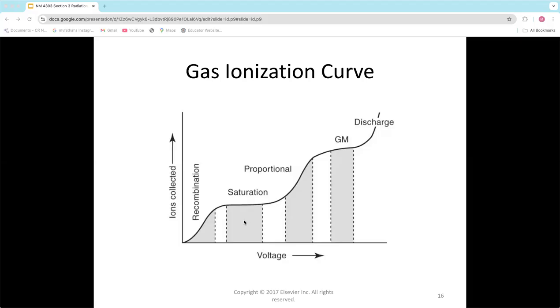So if you have a meter, and you're doing a treatment with I-131, and you need to measure your patient's rate before they leave, you're using an ionization chamber because it's giving you a measurement. It's collecting and gathering and constantly getting data and giving you a measurement. That's a way to think about it. You're using something in the ionization or saturation range when you're able to actually get a measurement out of it.